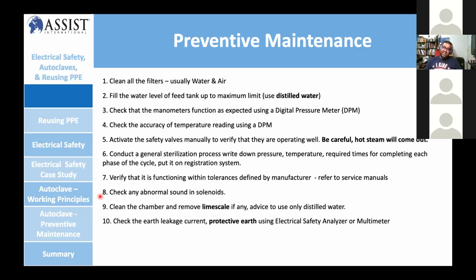Now lime scale: you can see what happened to the heating element. On the heating element you can see a lot of lime scale, and some of the piping is full of lime scale as well. All this can cause blockage, and maybe the copper pipes get blocked. Initially, your autoclave is not going to complete the full cycle according to the setting, and it's going to fail. So always check whether the heating element has lime scale. Always use distilled water, and make sure you clean the heating element.